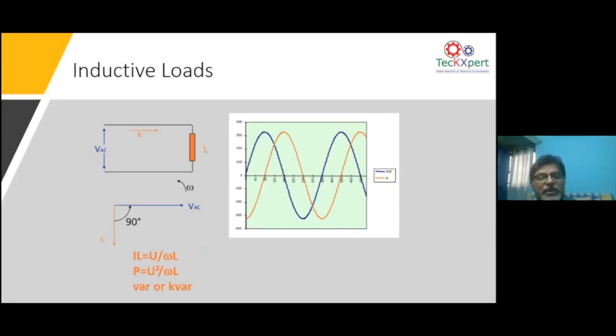The power equation you can apply very easily to an inductive network or a capacitive network, and you can easily calculate what the inductance value or capacitance value is. Here, if somebody wants to know the inductance of a coil, when you know the kVAr, you can take kVAr equals voltage squared divided by 2 pi FL. That is how we calculate that.